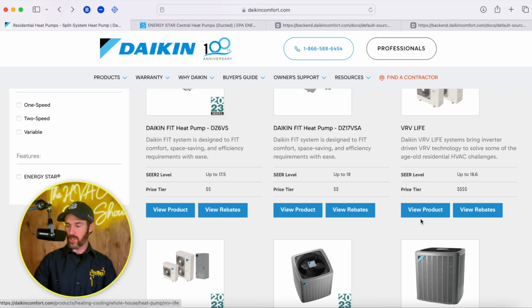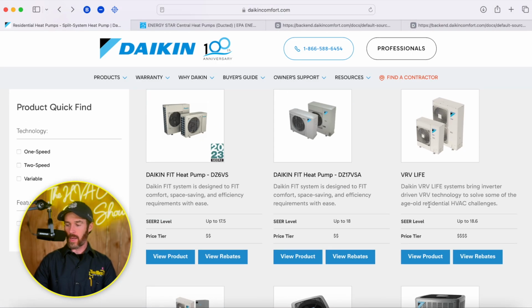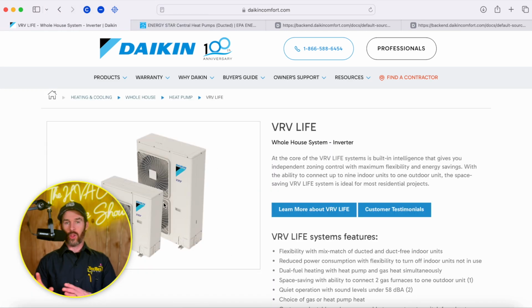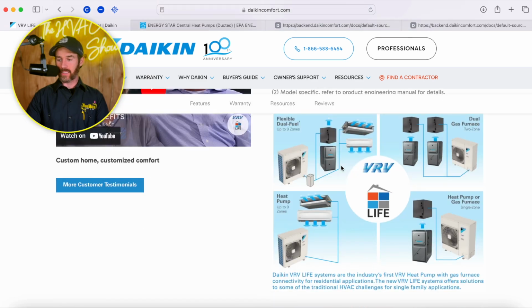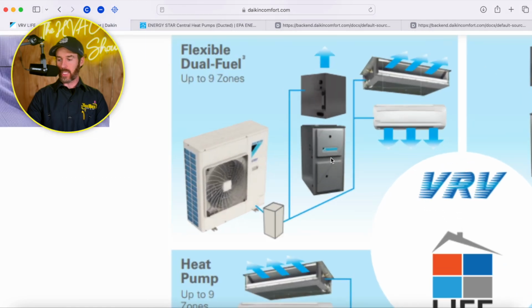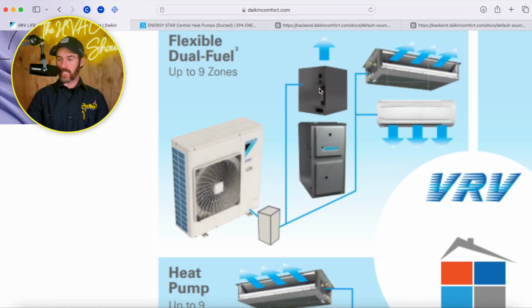Now, the VRV Life is another product I'll talk about briefly, and why you'd go with this. The only difference is that this is a variable refrigerant flow product. This system can communicate with up to 16 head units depending on the size. So if you have one condenser outside, you could have an indoor furnace connected with an evaporator coil, a slim ducted unit that's concealed and can go in a tight attic or crawl space to serve a certain part of the home, or an air handler.